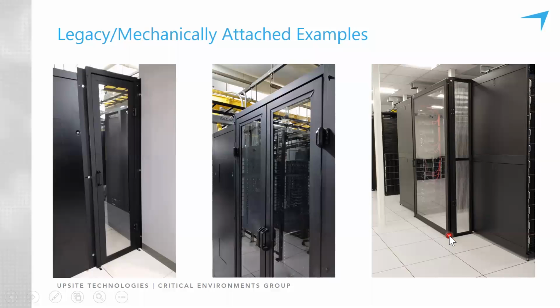The single sliding doors, like you see in the picture, are designed to either slide to the right to open or to the left to open. So this one would obviously slide to the left to open. This one also shows one of those return panels for an offset aisle. But the double sliding doors are very popular. They're made to accommodate a variety of different cabinet heights and widths of the aisles. And the doors oftentimes come with a stay open feature so that you don't have to hold them open, and then either a slight tug or a quick push on the door, depending on which manufacturer you're using, they'll close automatically and gracefully shut so they don't slam into one another.